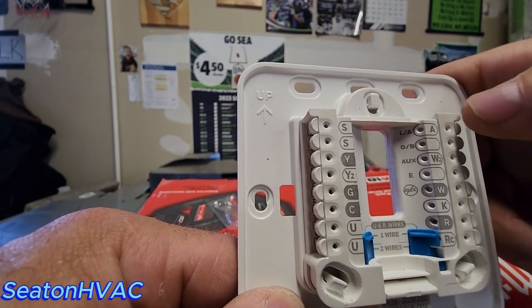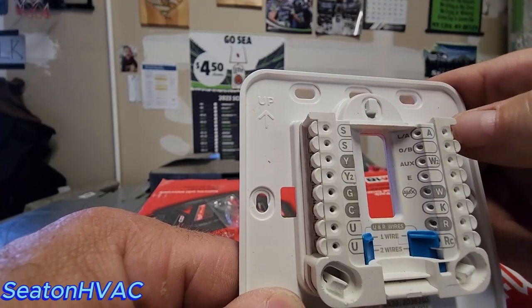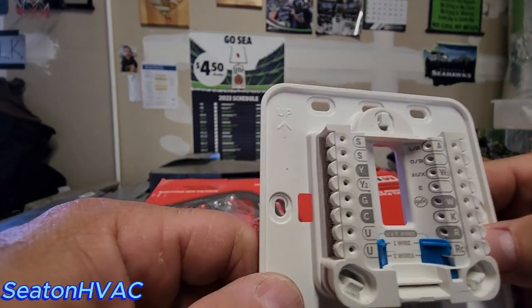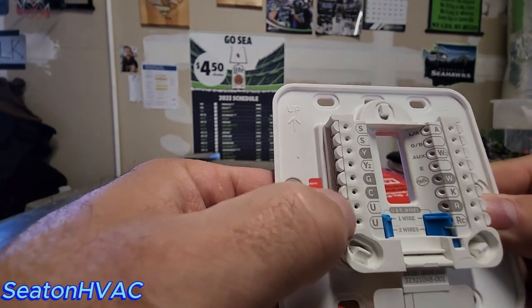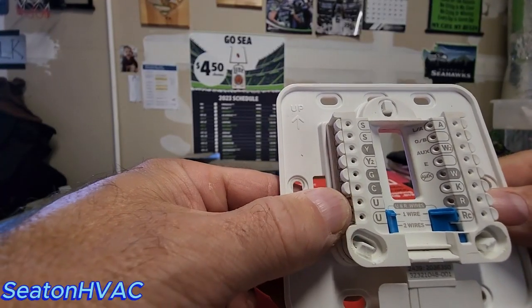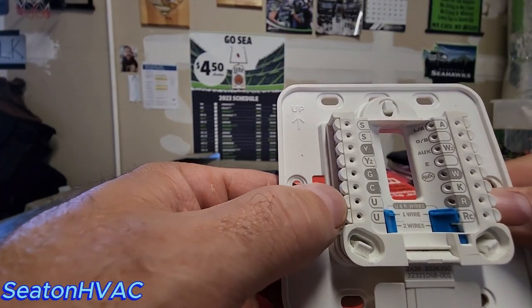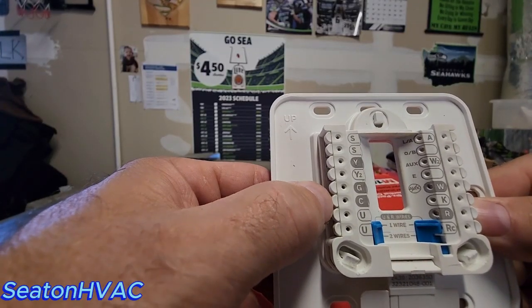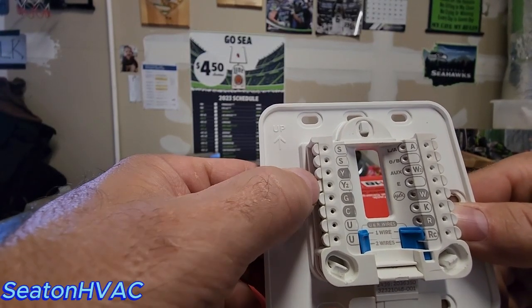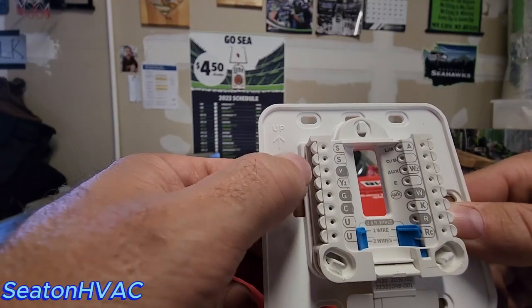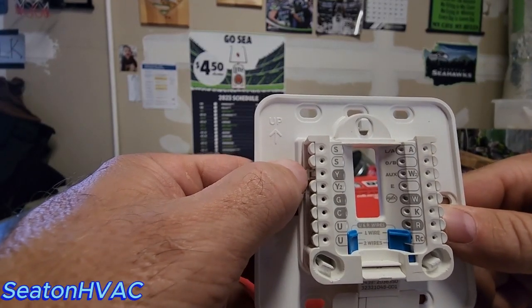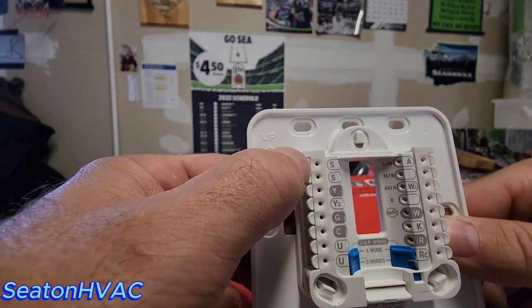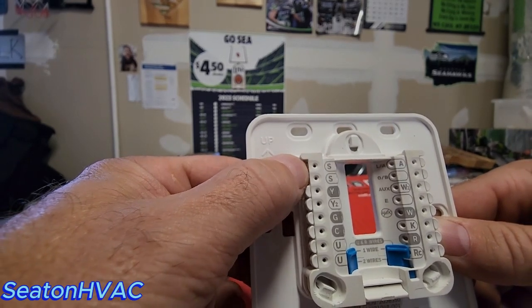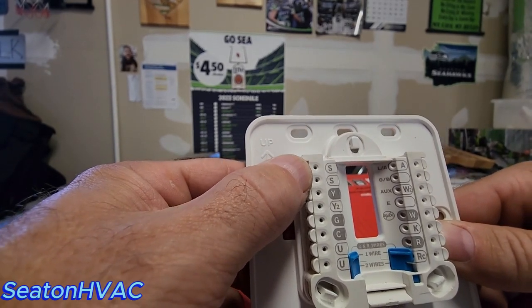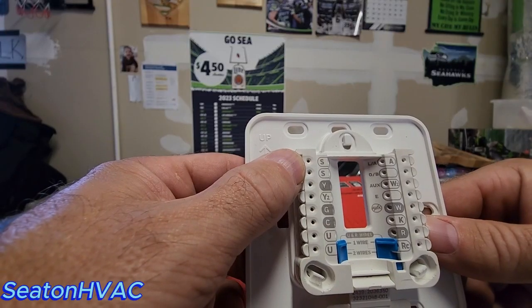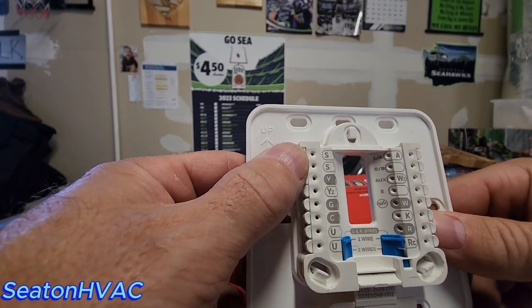O/B, that's your reversing valve. That's for nothing that you're going to use. It's for like a monitoring light or something. You got your U and U if you got some contacts there for like a humidifier or an accessory. You got your common. You got your G, that's your fan. You have your second stage compressor, which is Y2. You have your first stage compressor, which is Y. And then if you have an outdoor sensor that you want to add to the system, that's what these terminals are for, S and S. For staging your backup heat if you want to set a lockout temperature or something.